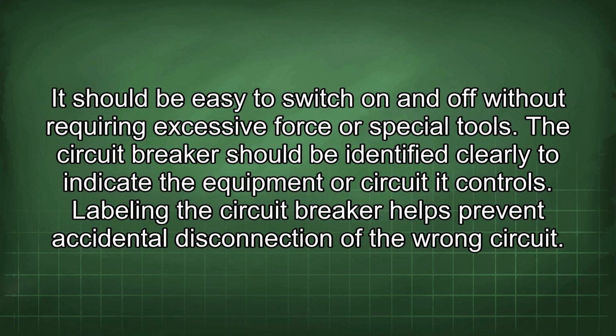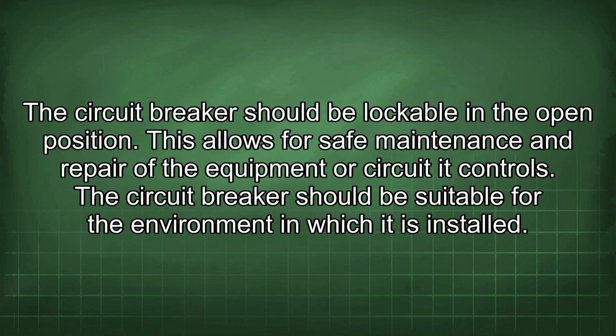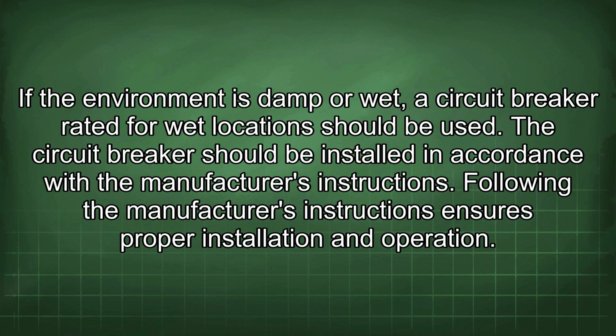The circuit breaker should be identified clearly to indicate the equipment or circuit it controls. Labeling the circuit breaker helps prevent accidental disconnection of the wrong circuit. The circuit breaker should be lockable in the open position. This allows for safe maintenance and repair of the equipment or circuit it controls. The circuit breaker should be suitable for the environment in which it is installed. If the environment is damp or wet, a circuit breaker rated for wet locations should be used.